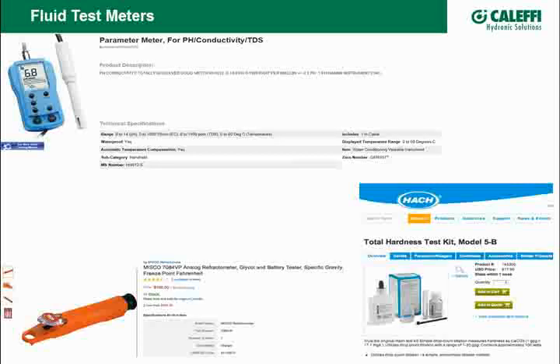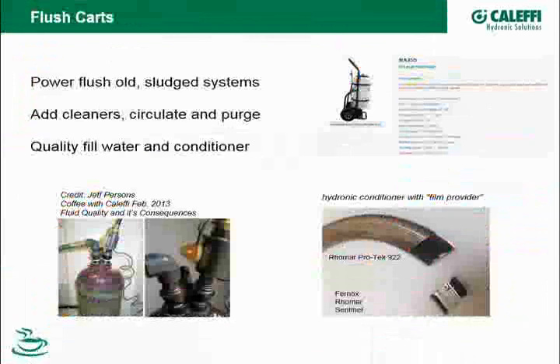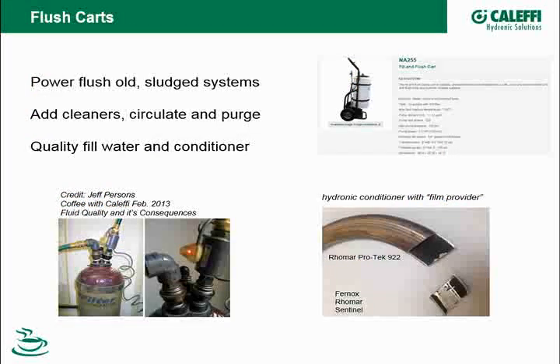Now, if you are going to start using inhibitors, and I think maybe I've got that on the next page. If you're going to start using different corrosion inhibitors or different hydronic system inhibitors, you'll have to get a test kit from the manufacturer that can test that. And sometimes there are little jars that work similar to that hardness test kit. Some of them have little electric meters that you can put in there, because it's going to be a meter that's going to test specifically the ingredients or the inhibitors that they're putting in that fluid. And there's a lot of different types of inhibitors that have been used over the years for conditioning hydronic systems. So make sure that the kit that you're using matches the fluid that's in there.